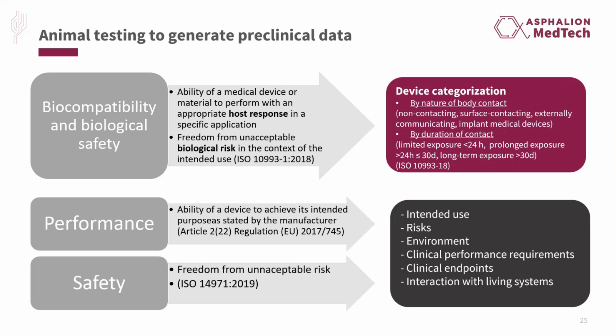In biocompatibility and biological safety, the device categorization is very relevant. The device categorization is defined by the nature of body contact or by the duration of that contact. While in performance and safety testing, we should have a very well defined intended use of the device. We need to evaluate risk in this animal testing, and the environment. We should also know the clinical performance requirements. This testing should reflect as much as possible the clinical endpoints of a future clinical investigation, and this type of testing will also assess the interaction of the device with living systems.